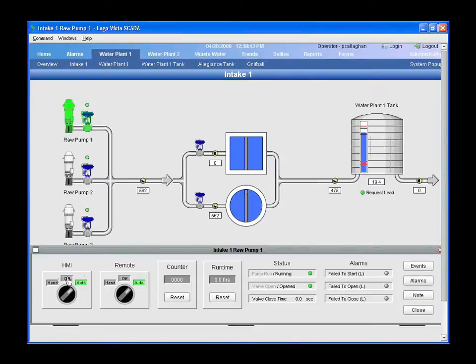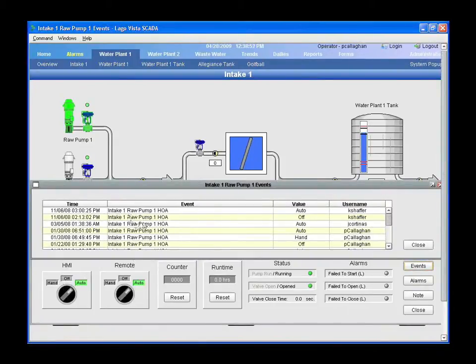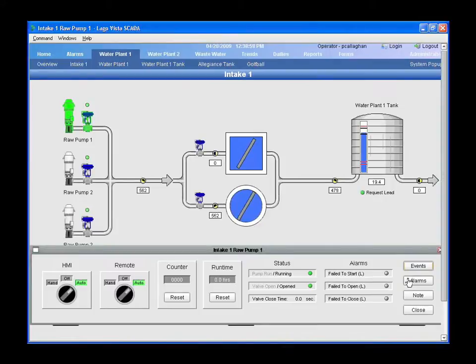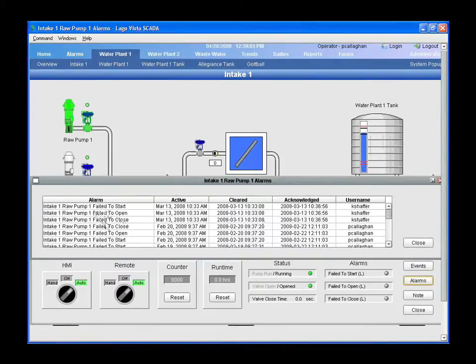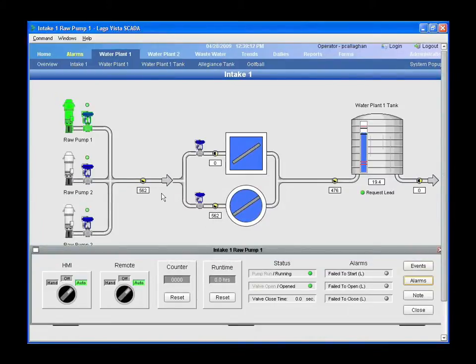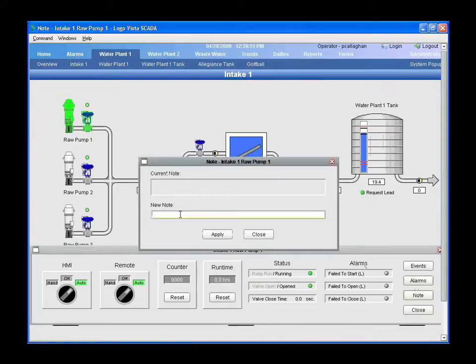Operators have access to all the pump status, information, and alarms. We record all events — when every operator makes a change to the system, it gets logged: what they did and who did it. I also have alarms for each individual item. This shows only the alarms for this one pump — when it was active, when it was cleared, who acknowledged it. We can also add notes onto an individual pump.